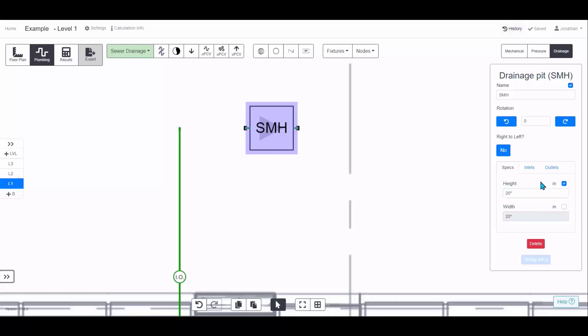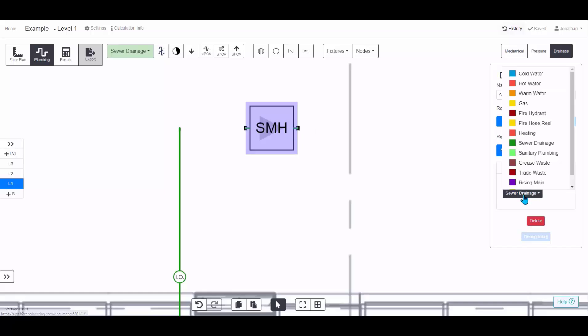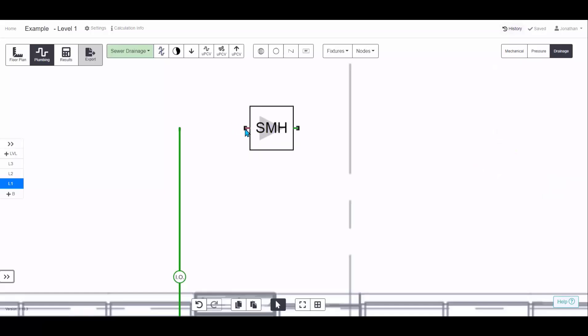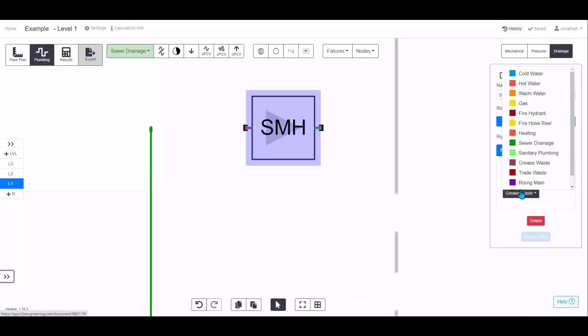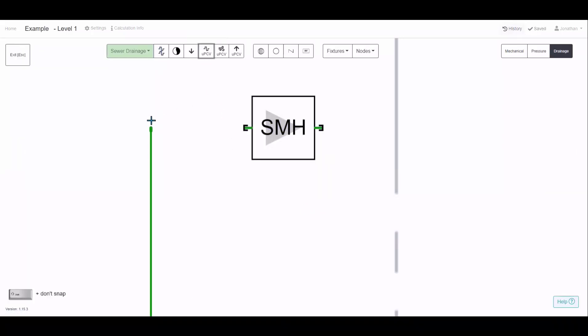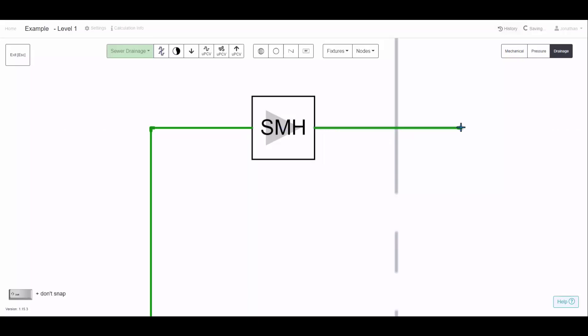You can change visually how it looks. If you want it to be more of a square, you could do 20 by 20. And then from there, just choose what inlet you'd like. So the inlet's on this side of the triangle, and the outlet is on the other one. So at the moment, both are set to drainage, but if you, for example, have like trade waste or grease waste coming into it, you'd want to select that for the inlet, and then on the outlet it would change. But for now, we'll leave it as drainage. And then from here, just select the flow system you'd like, and then connect up. Once that cap disappears, it's connected, and you can carry on drawing as well.